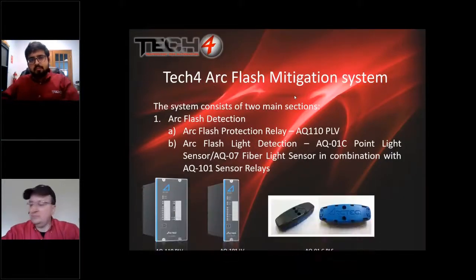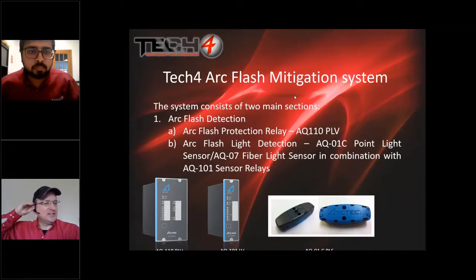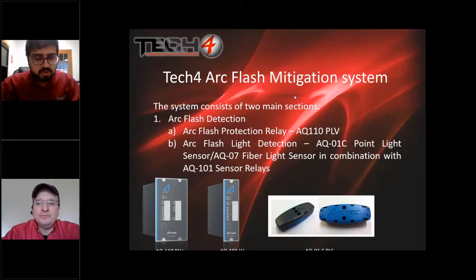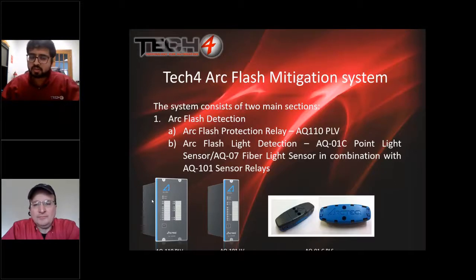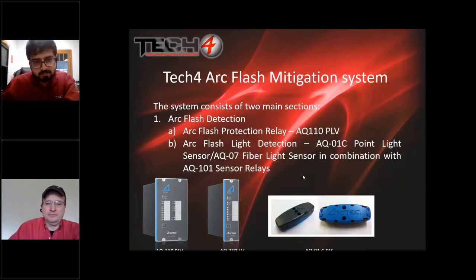So the Tech4 arc flash mitigation system consists of two main sections. One is the arc flash detection, and the other is the arc quenching. The arc flash detection is done through the arc flash protection relay. It's pretty much the brain of the arc flash mitigation system. It senses light plus current and sends a trip signal to the arc quencher AQ1000 device, which I'll be showing in the next slide. So all of this process happens under 4 milliseconds.